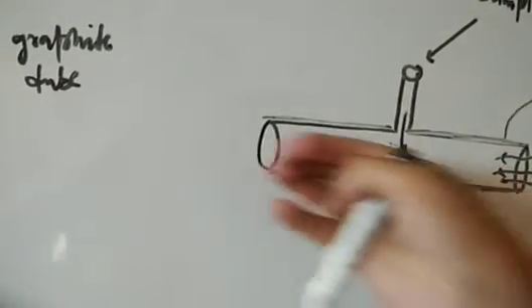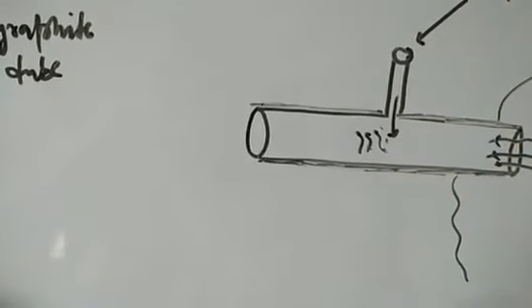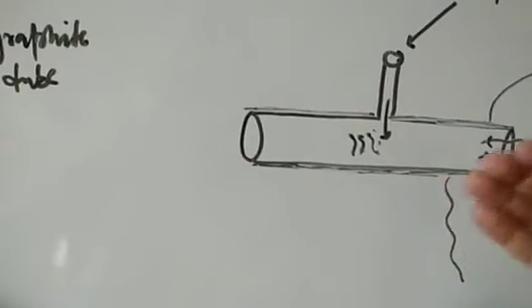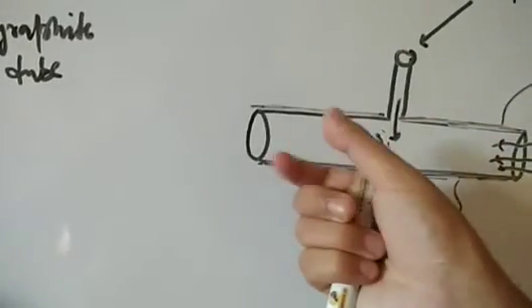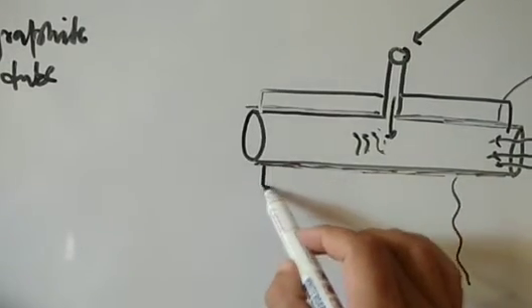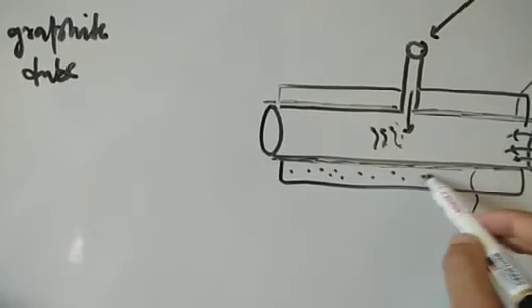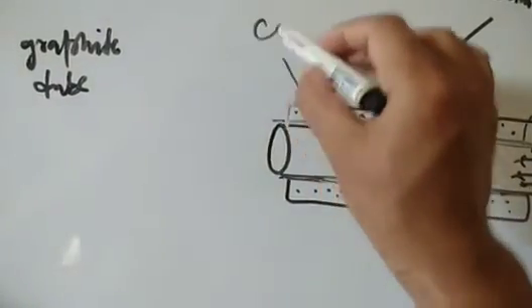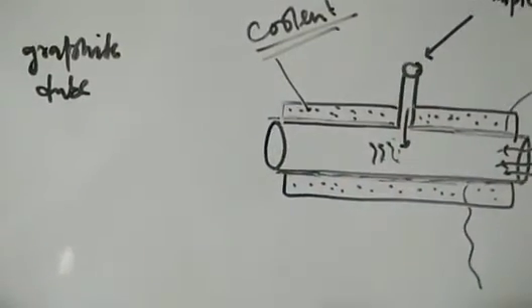An inert gas also flows through the tube. The inert gas helps to remove volatile impurities and the solvent as the temperature rises. Additionally, because of the very high temperatures there is a risk the tube may burst, so a coolant or water supply is used. Outside the tube there is another casing where the water supply flows as a coolant, to prevent bursting and keep the temperature of the graphite tube controlled during the heating process.